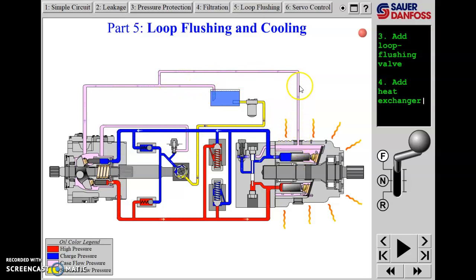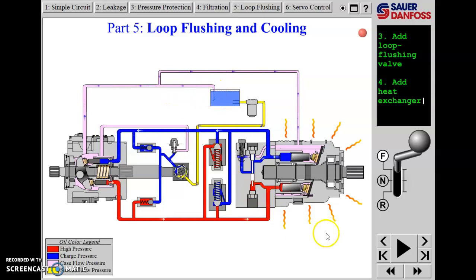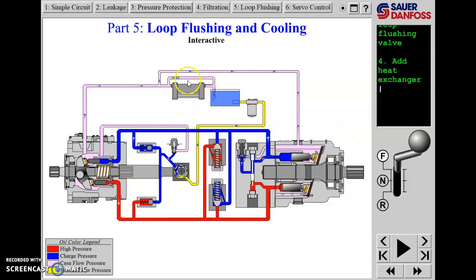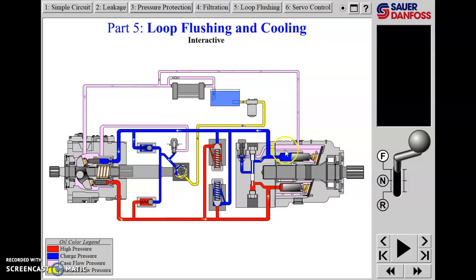On the Sundstrand unit in the main shop, the oil coming out of the motor actually goes around to the far side of the pump, flushes through the pump case, and takes heat out of the pump case as well — with one line heading back to the reservoir. That's a slight difference from this animation to what we have in the iron. They're also going to put a heat exchanger — an oil cooler — in here. This illustration shows a water-to-oil type heat exchanger, but it could be a radiator type — some method of exhausting the heat collected via the flushing shuttle and relief.